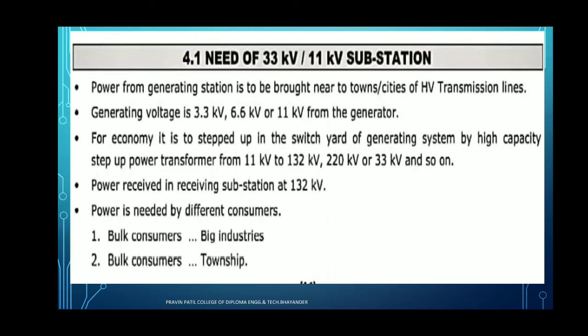So first we have to see the need of 33 by 11 kV substation. Why are 33 by 11 kV substations required? Why is this substation needed? First point, the power from the generating station is to be brought near to the town or cities by high tension transmission lines. Generating voltage is near about 3.3 kV, 6.6 kV or 11 kV from the generators. For the economy, it is stepped up in the switchyard of the generating system by the high capacity step up power transformer from 11 kV to 132 kV or 220 kV or 33 kV and so on.